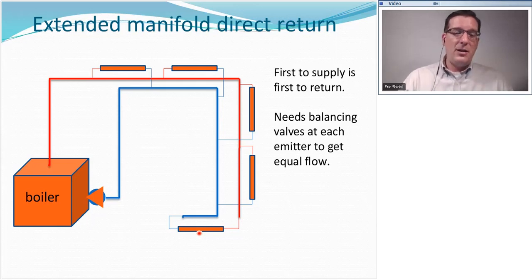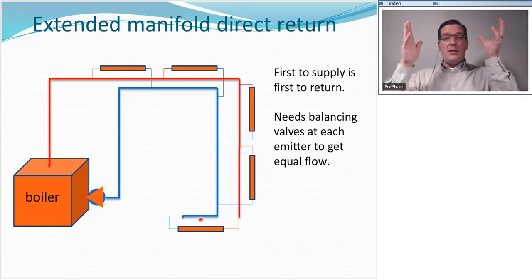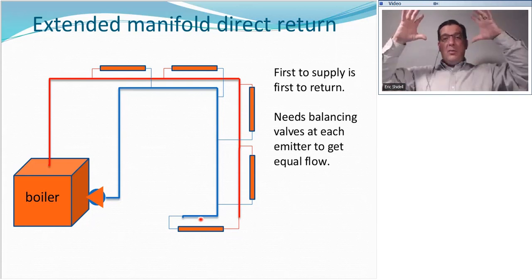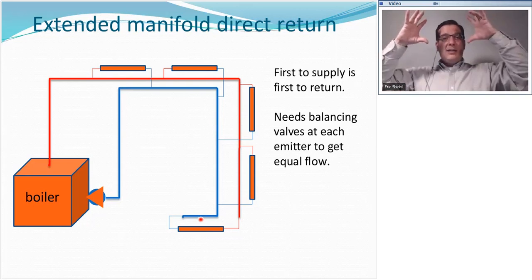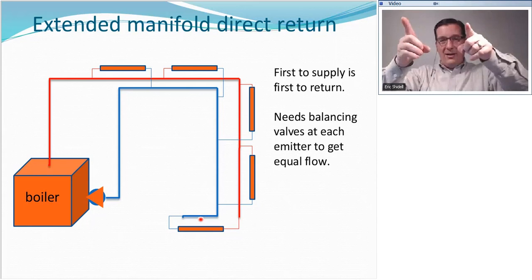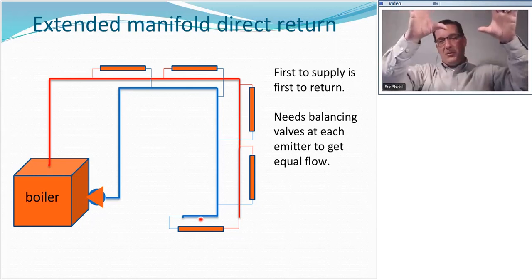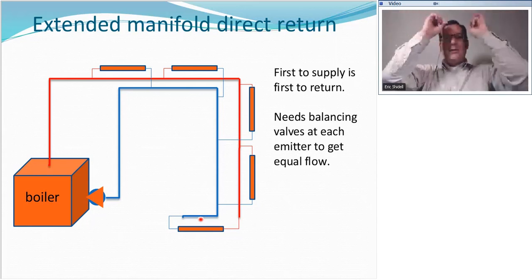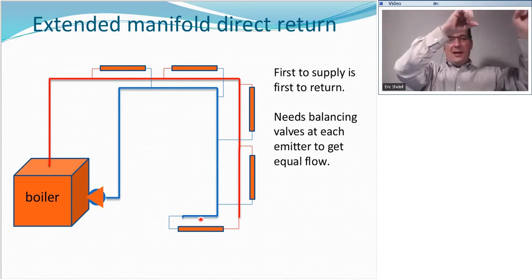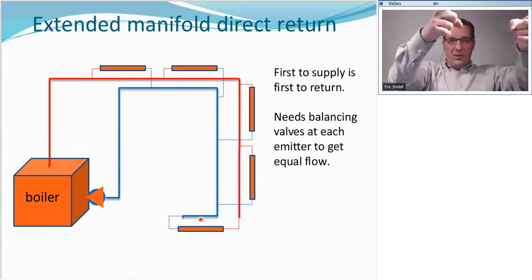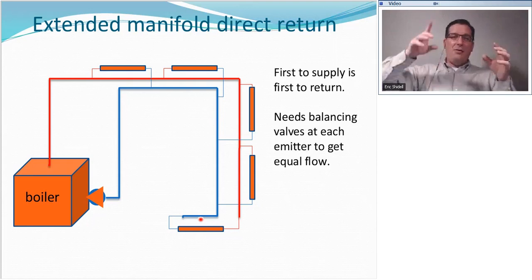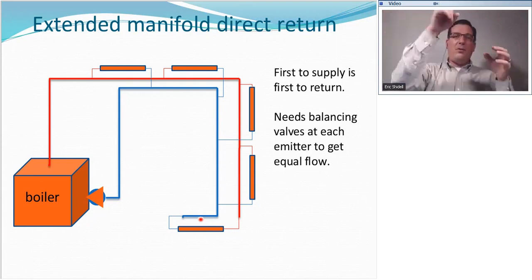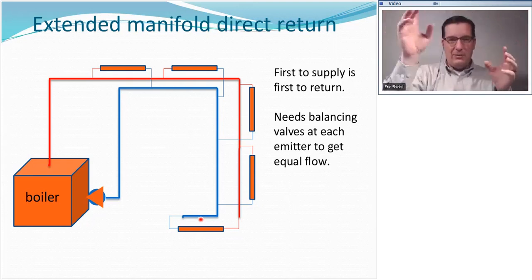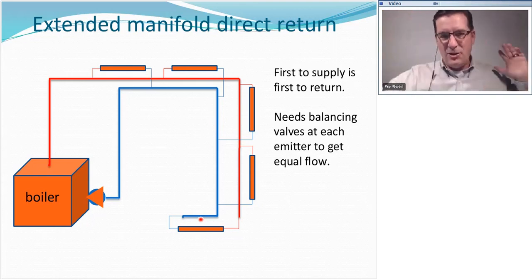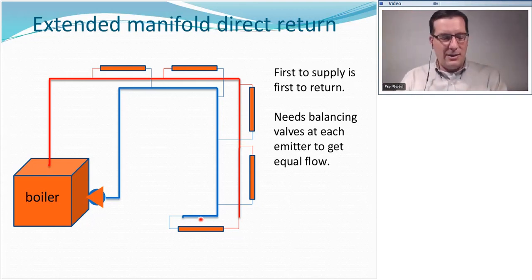And you'll always recognize an extended manifold reverse return when you stick your head up in the ceiling and you see a great big old pipe with a label that says heating supply and arrows going that way. And then right next to it is another big pipe of equal size that says heating return with arrows going that way. And right next to that is another pipe that says heating return with arrows going that way. So you can kind of envision the water going out, going this way, and going back in kind of like a big, long, elongated S-shaped snake. That is that extended manifold reverse return.